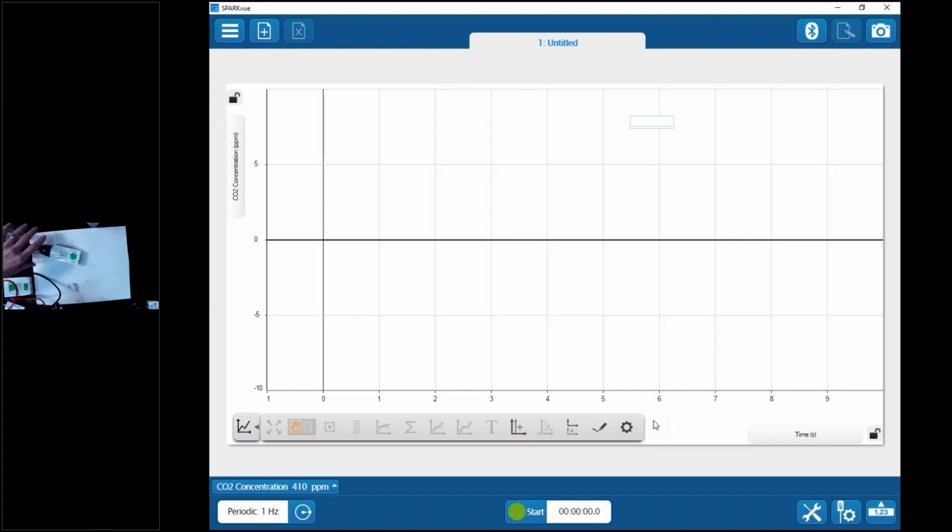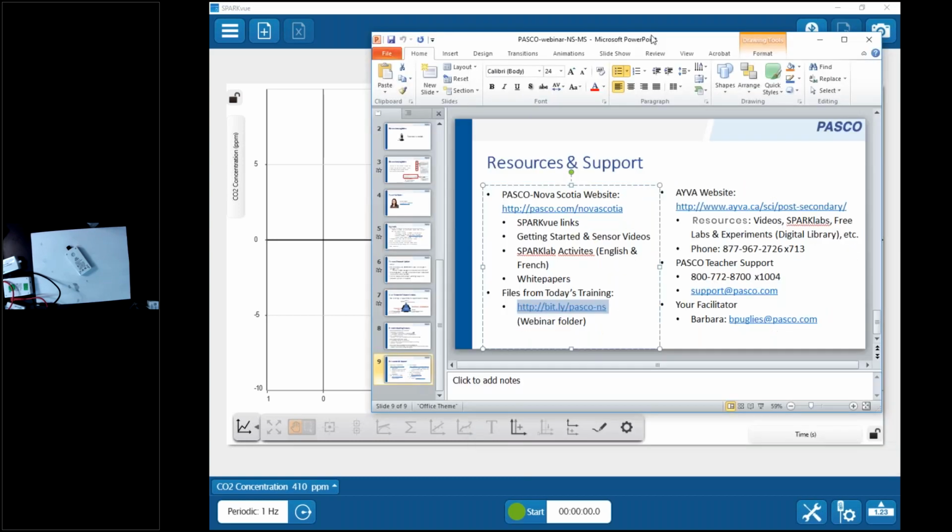Okay, but if I want to know a larger area, or I want to know just what's the light level in the room, then I need to flip the sensor over to make sure that this sensor that says ambient is getting a reading from the whole room. Okay, sorry for the brevity of that discussion on those sensors, but I'm running short of time.